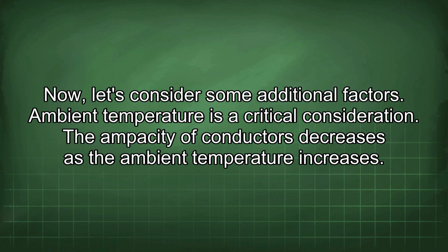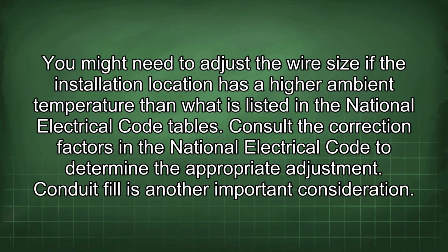Ambient temperature is a critical consideration. The ampacity of conductors decreases as the ambient temperature increases. You might need to adjust the wire size if the installation location has a higher ambient temperature than what is listed in the National Electrical Code tables. Consult the correction factors in the National Electrical Code to determine the appropriate adjustment.